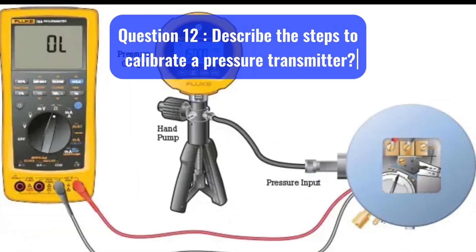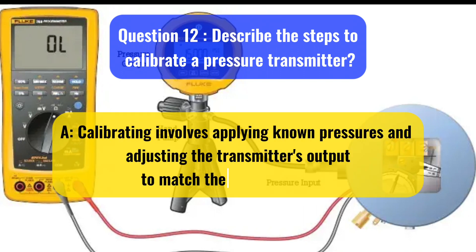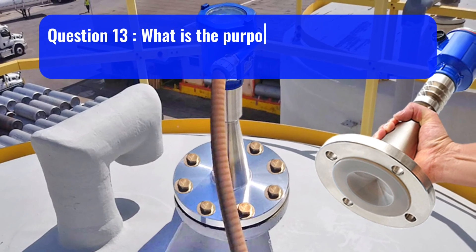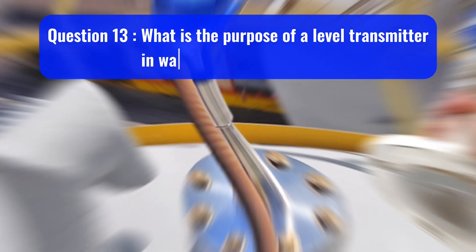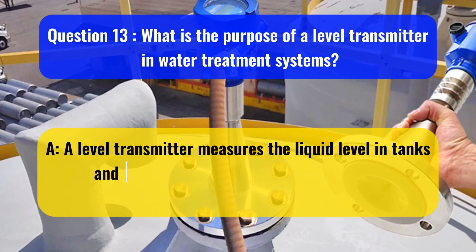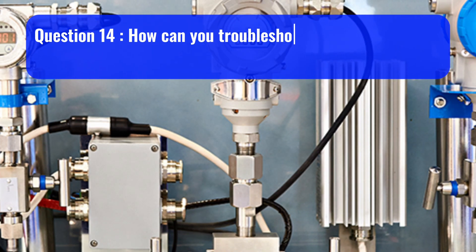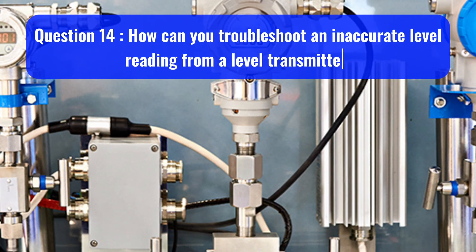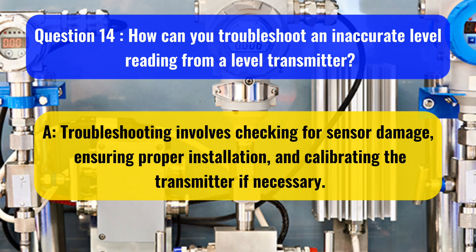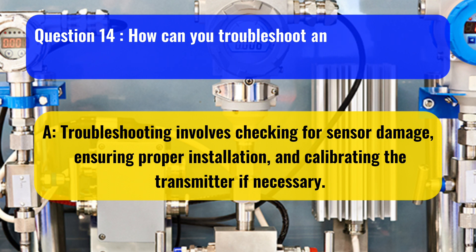Question 12: Describe the steps to calibrate a pressure transmitter. Calibrating involves applying known pressures and adjusting the transmitter's output to match the expected values. Question 13: What is the purpose of a level transmitter in water treatment systems? A level transmitter measures the liquid level in tanks and basins, providing data for control and monitoring purposes. Question 14: How can you troubleshoot an inaccurate level reading from a level transmitter? Troubleshooting involves checking for sensor damage, ensuring proper installation, and calibrating the transmitter if necessary.